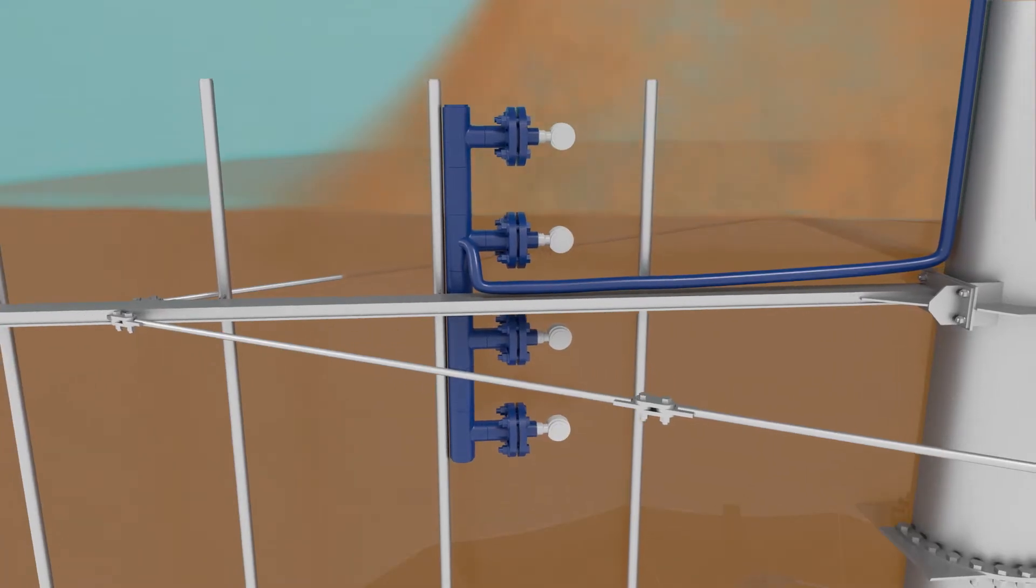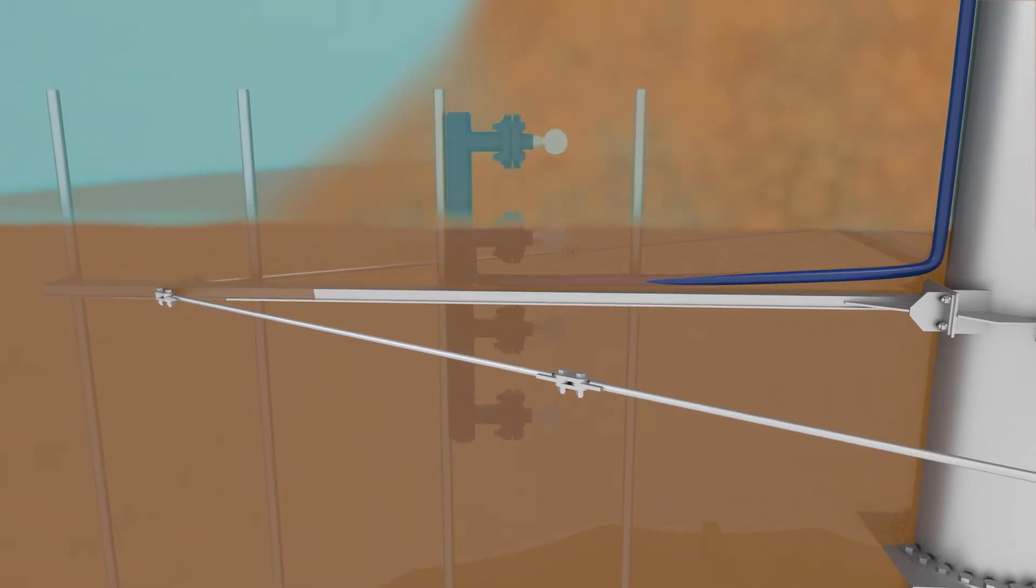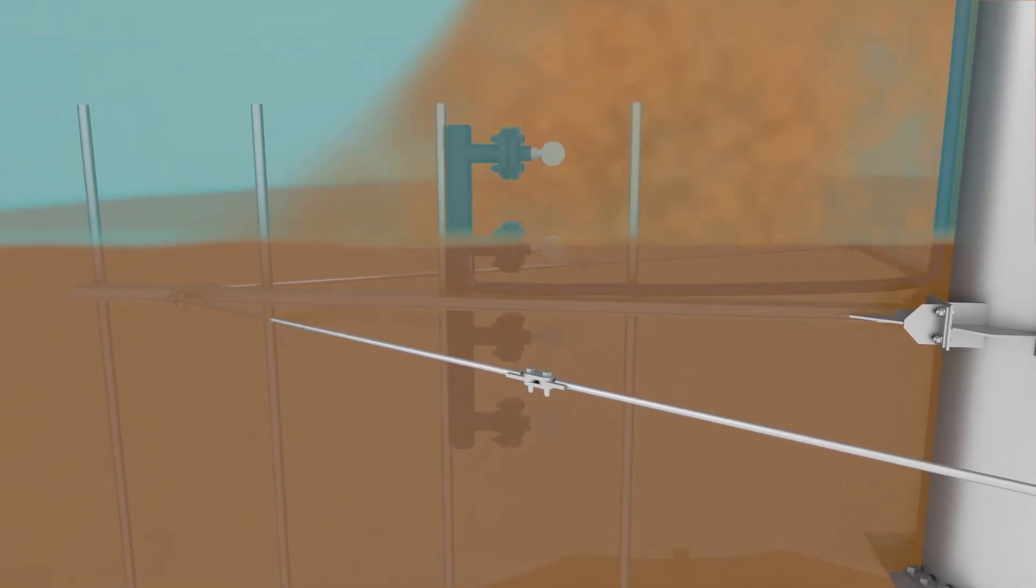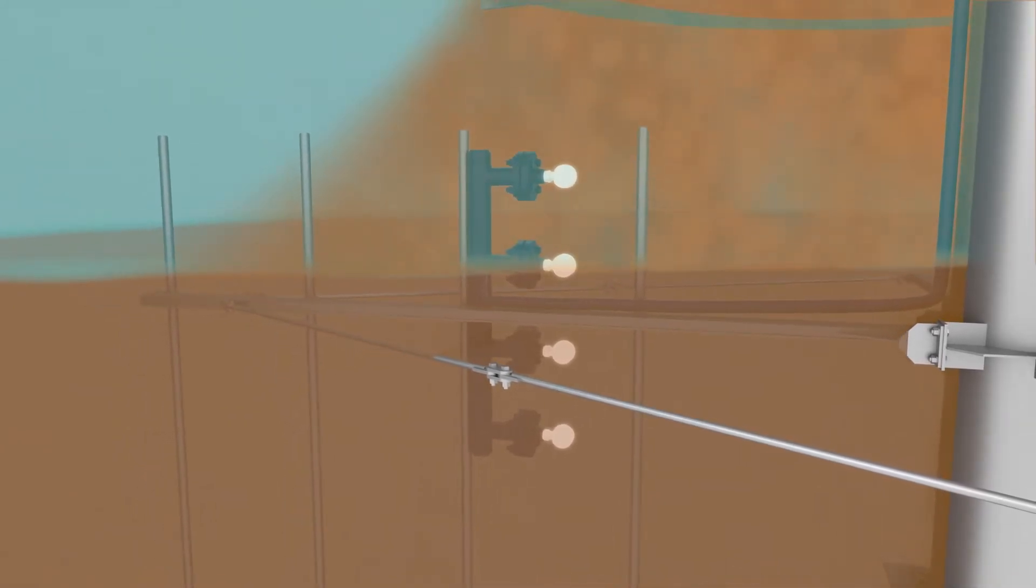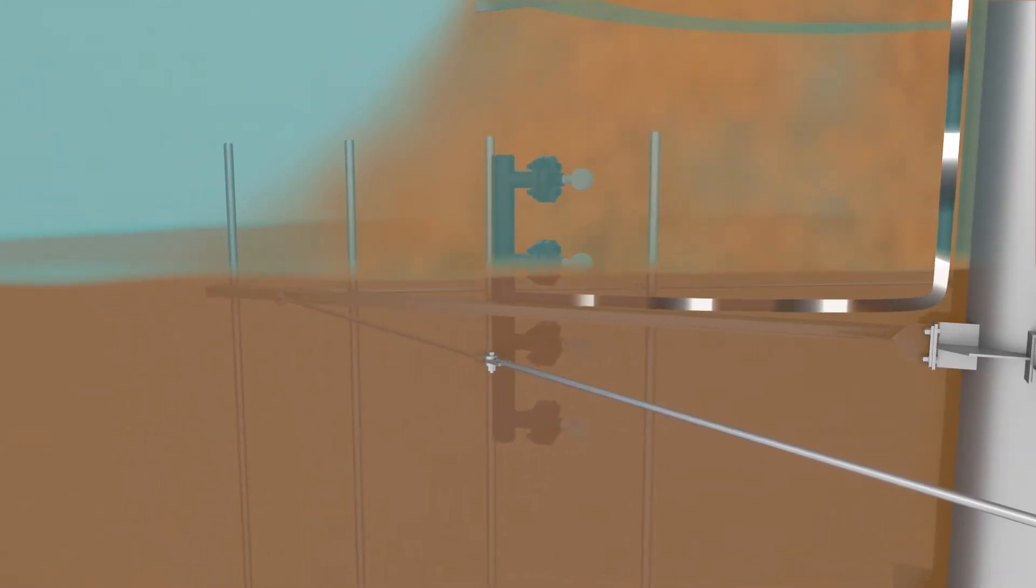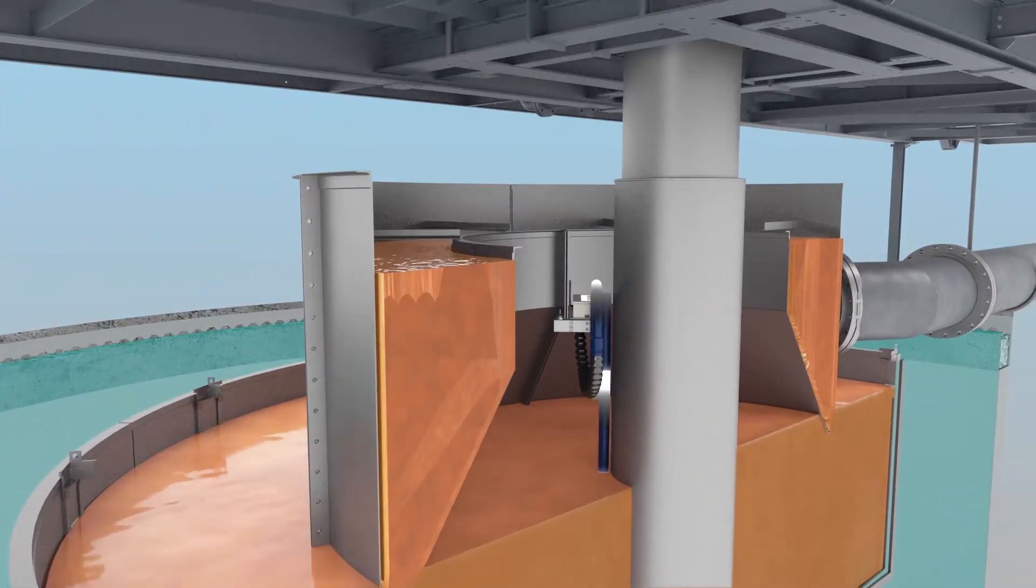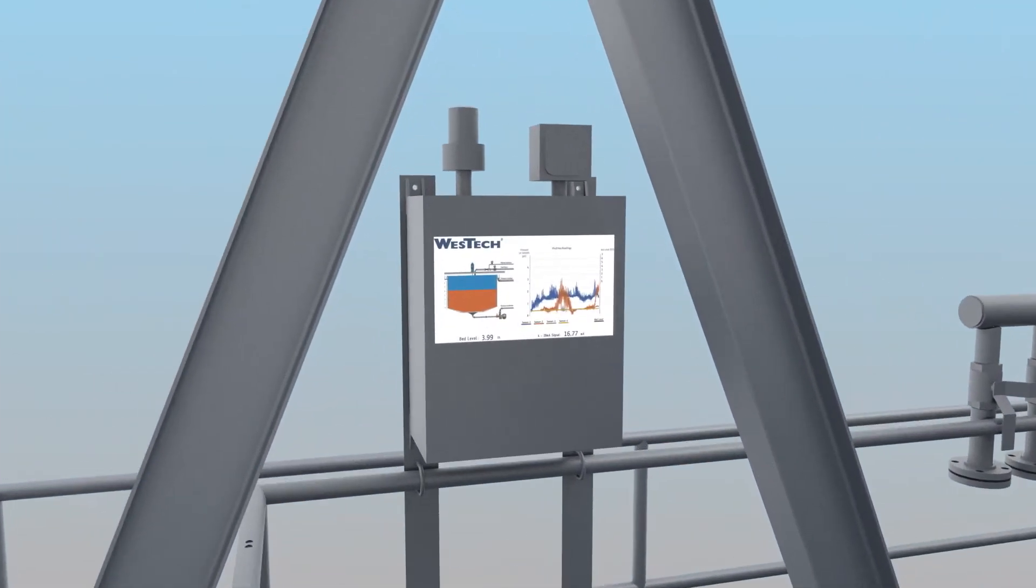The Mud Max attaches to the tank's rake mechanism. As the rake rotates through the thickener, multiple sensors located in the active bed level area pass through the compacting solids of the bed. Data from each sensor is wirelessly transmitted to a receiver located on the bridge, producing an accurate bed level measurement around the entire thickener.